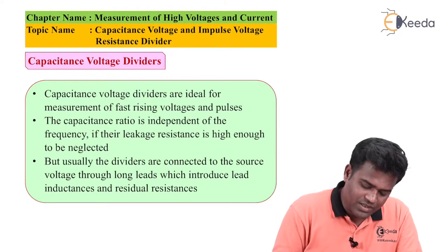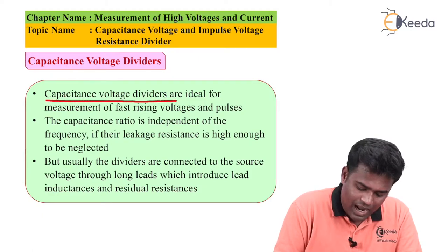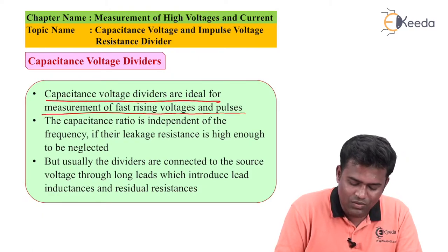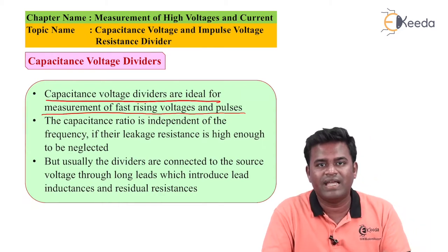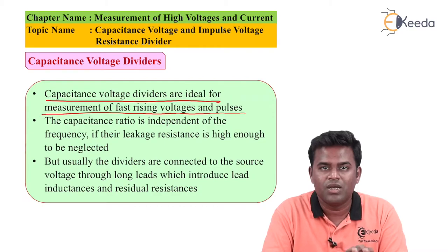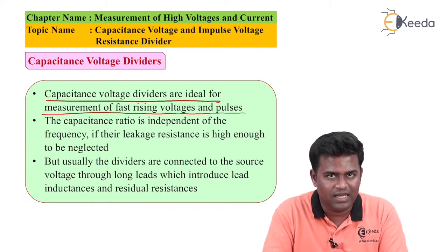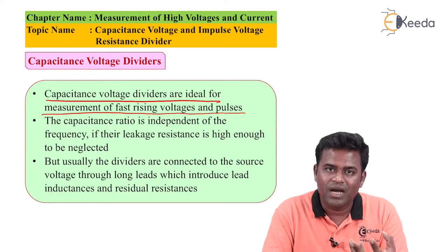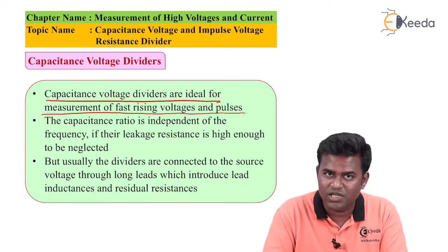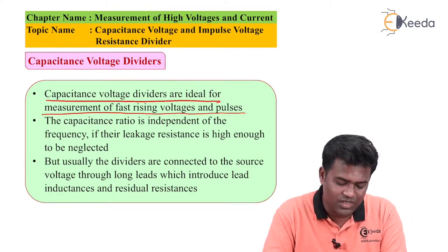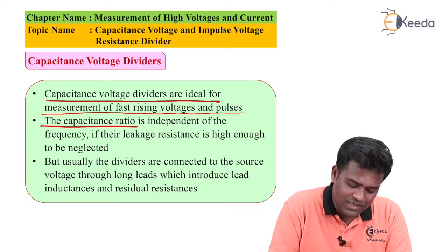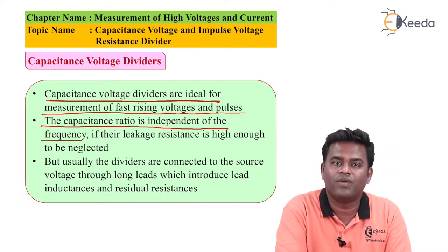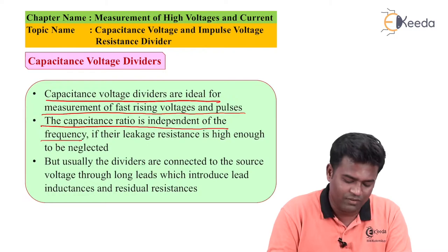The capacitance voltage dividers are ideal for measurement of fast rising voltages and pulses. In a system when there will be disturbances, pulses are created. The transients in the system unbalance the voltage so rising voltage occurs, and that is when we use a capacitance voltage divider. In that case, the capacitance ratio is independent of frequency — it does not depend on frequency.